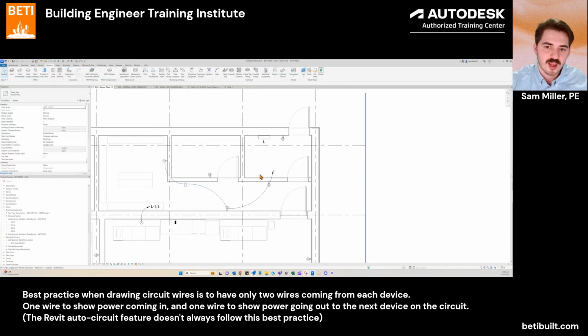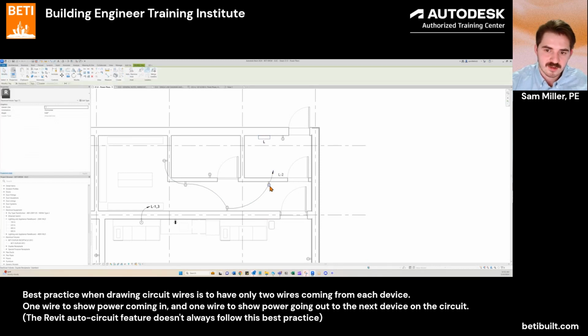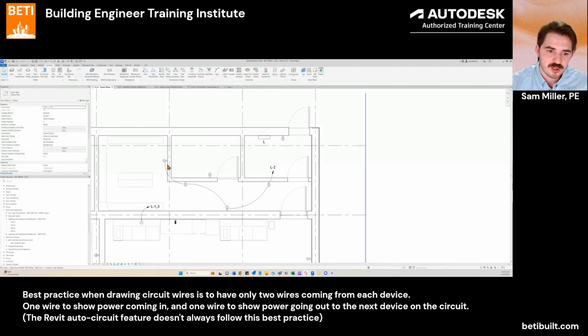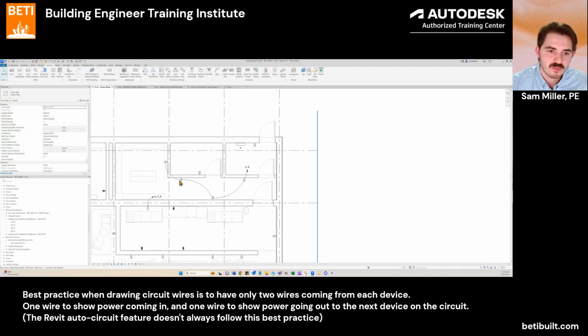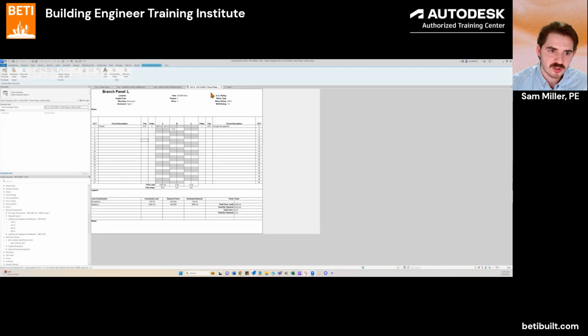I'll hit arc wire, and now it does the circuiting for me - it draws the home run automatically, and it's smart enough to draw it closest to the panel. Then I can tag the circuit, drawing it here, and now you can clearly see which circuits are together. If I go back to my panel schedule, since I edited it earlier, it will now say storage receptacles.